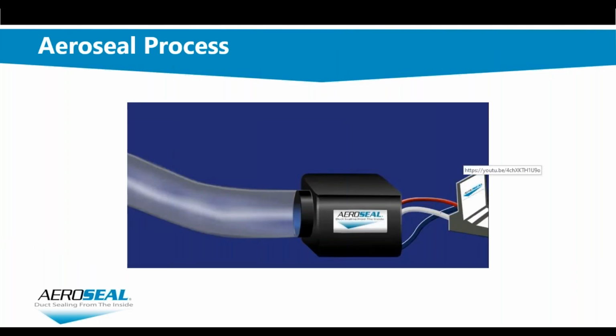So the way that we conduct that sealant material to the injection point, you'll see the Aeroseal system here. The laptop shows wires going to it, but it is wireless. The lay flat tubing, the plastic tube that comes off the front, goes to the injection point on the duct system. And while this process is occurring, those aerosolized particles go into the closed duct system where the equipment is isolated, and that's where it does its work, closing up the gaps.